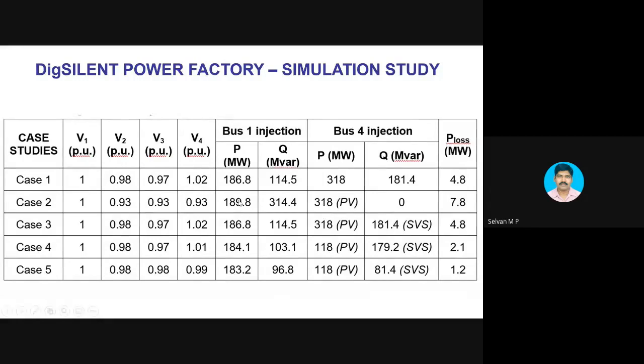Of course, now the real power is met and still I could observe that there is an increase in power loss compared to the first case. Even after replacing with PV, I'm getting an increase in power loss, though machine 1 is able to supply the additional loss. But what I observe is there is a loss of voltage. There is a huge drop in voltage profile. 0.98 has dropped to 0.93. 1.02 has dropped to 0.93, which is a critical situation.